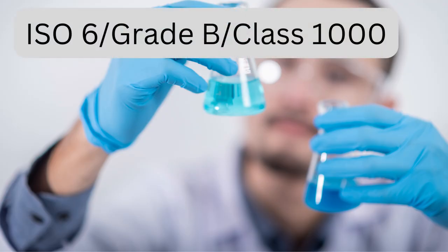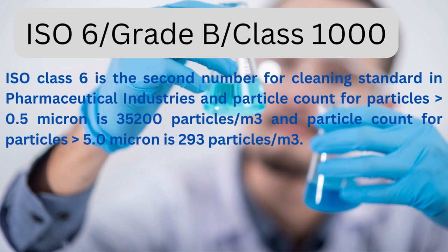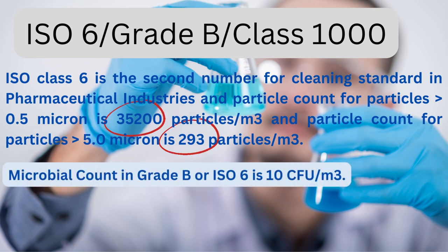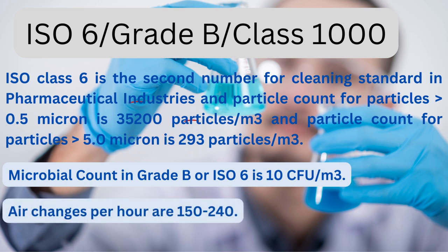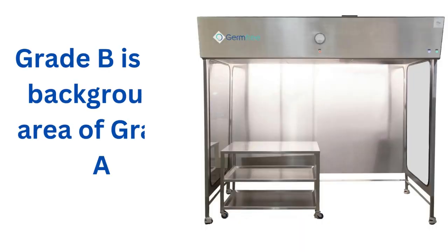ISO 6 corresponds to Grade B or Class 1000. ISO class 6 is the second cleanest standard in pharmaceutical industries. Particle count for particles greater than 0.5 micron is 35,200 particles per cubic meter, and particle count for particles greater than 5.0 micron is 293 particles per cubic meter. Microbial count in Grade B or ISO 6 is 10 CFU per cubic meter. Air changes per hour are 150 to 240. Grade B is the background area of Grade A, meaning the area in which the laminar air flow hood is placed.